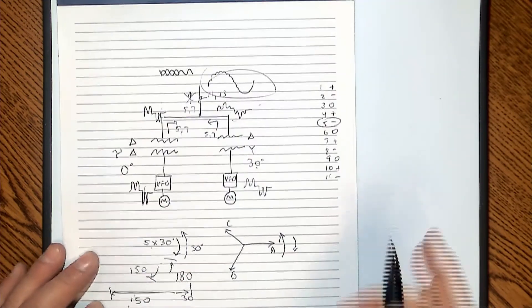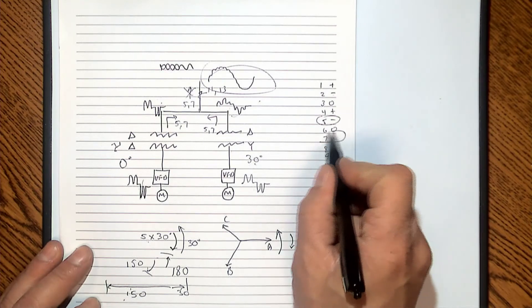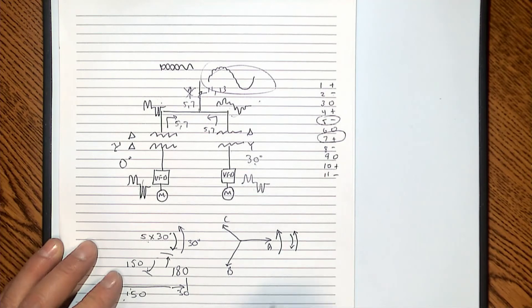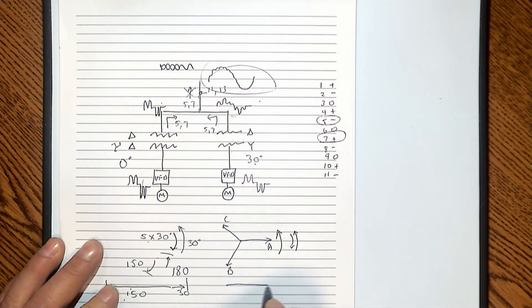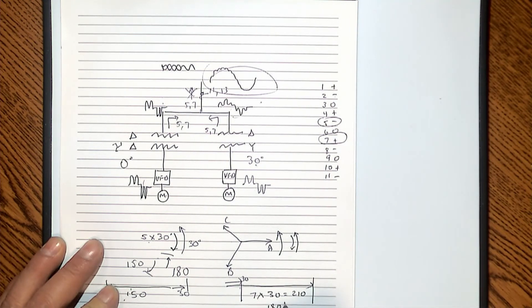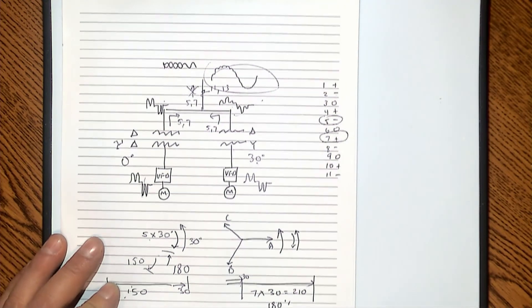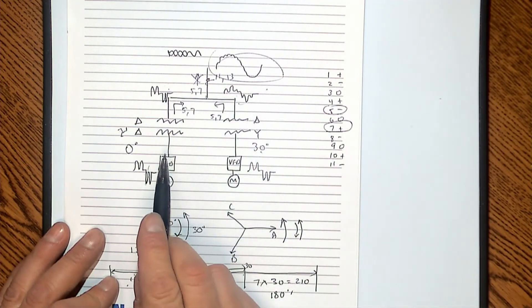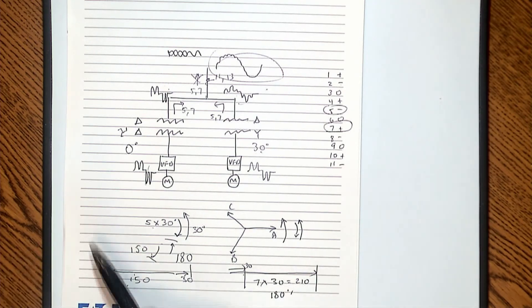For the seventh harmonic: because it is a positive sequence harmonic, it actually rotates the same direction as the 60 Hz fundamental. So imagine 7×30 = 210 degrees going in the same direction as 30 degrees with the fundamental — the net difference is again 180 degrees. So both the fifth and seventh harmonics coming up through the power system cancel out from both sides.